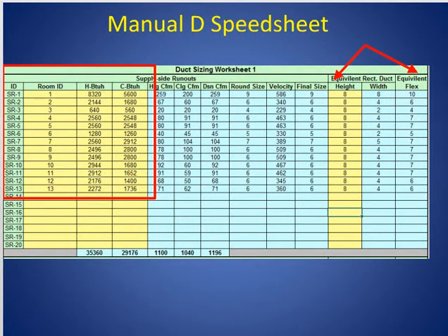The other thing I want to talk about on this sheet is the design CFM. That's not the balancing CFM. That's not what you balance to when you balance a system, because it's a rounded up number. It's based on the bigger of the 2, and so you'll never have that much air in a system, so you can't use that for that. That's just a design for duct calculations. It's not a design value for balancing.